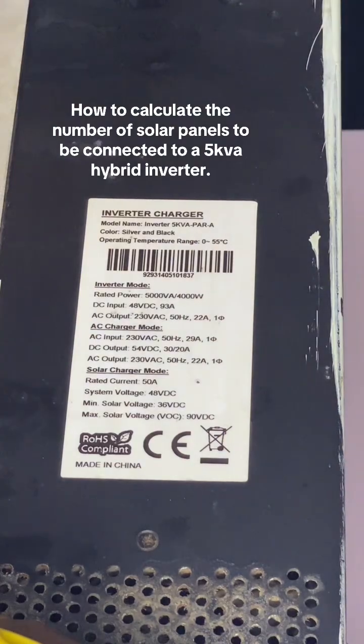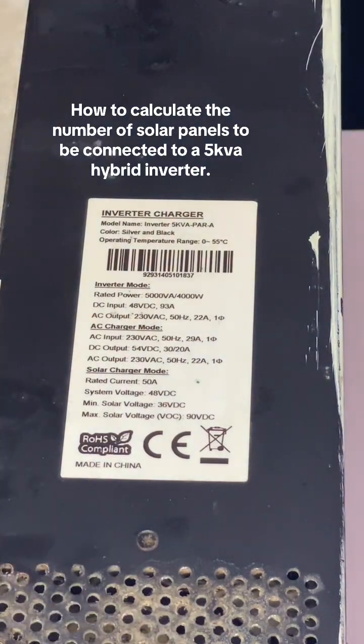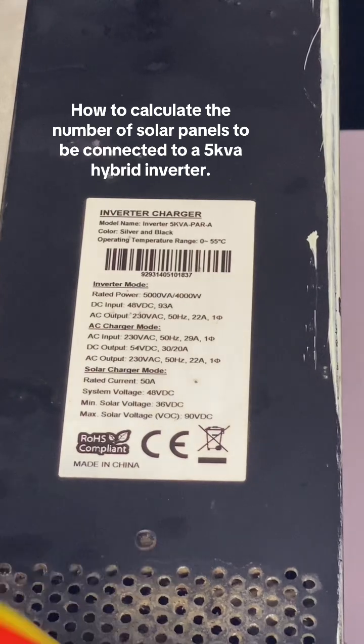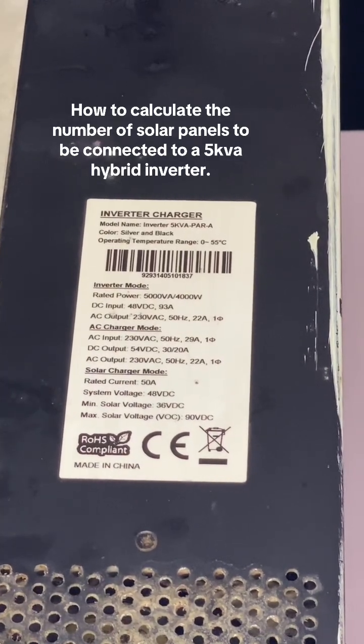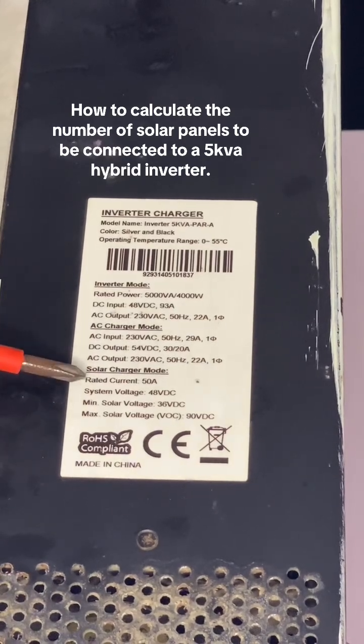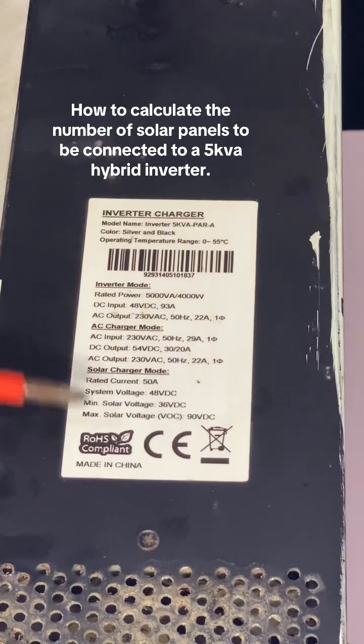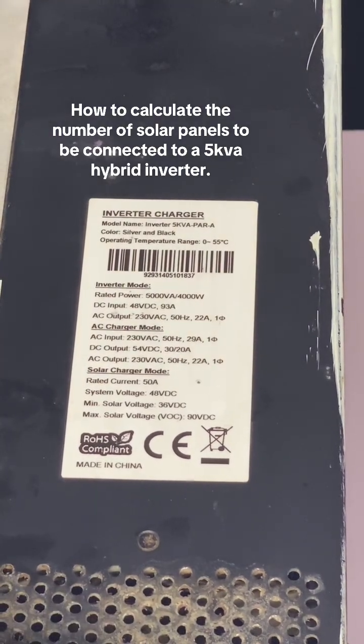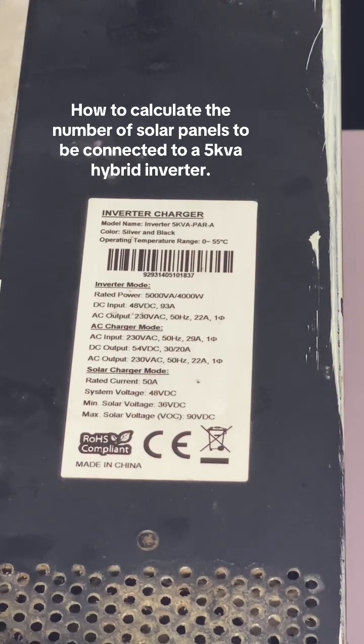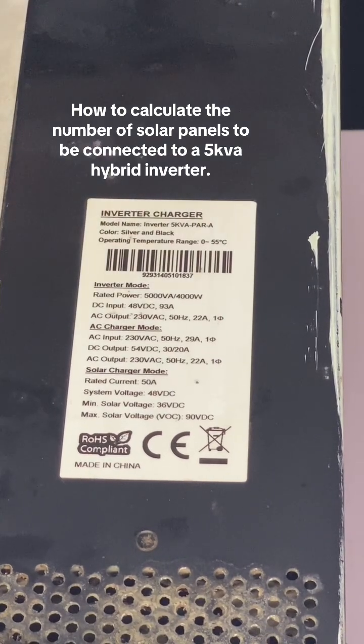When you connect two panels in series, you'll have about 70 volts at 12 amps. Now, 12 amps tells you how many panels you can connect in parallel to this inverter without damaging it. You divide your solar panel's current, 12, into 50. 50 divided by 12 gives about 4 point something, because 12 multiplied by 4 gives 48, which is within the range of 50.